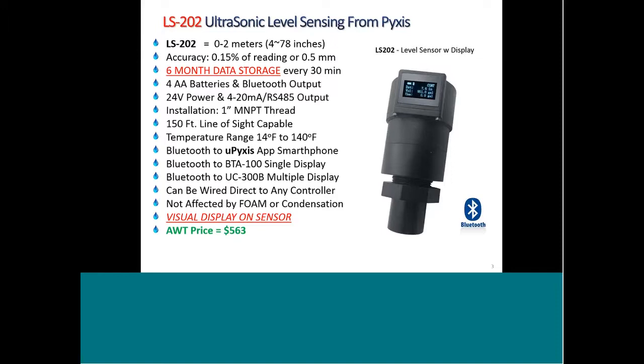What makes this sensor unique is that it can be both wired or operate in a wireless mode. On the back of the unit, in the next slide, you'll see there's actually a 7-pin quick connection. We provide a 6-foot cable, and we have cables extending up to 300 feet, which would enable you to wire this probe directly to any controller receiving a 4 to 20 milliamp or Modbus input. It would be powered in that operation mode by the controller.